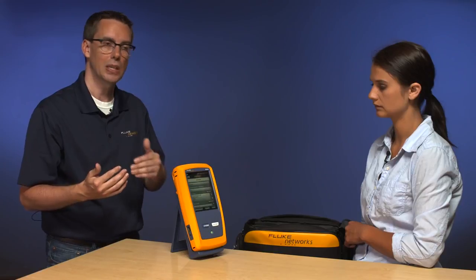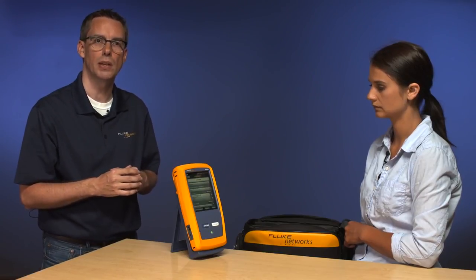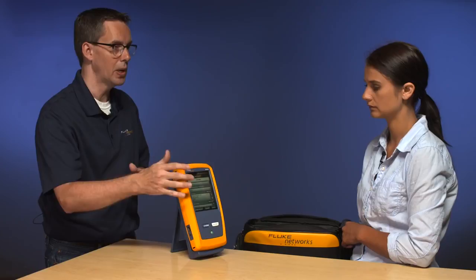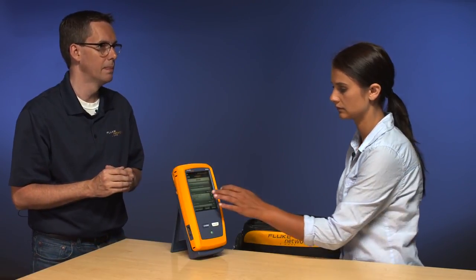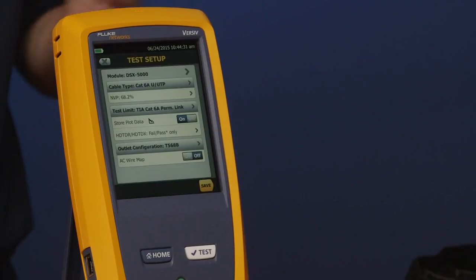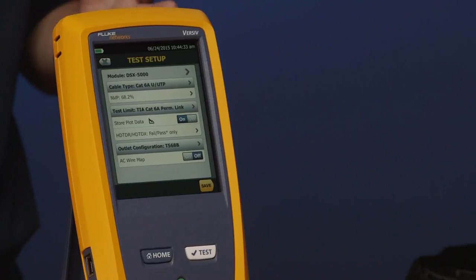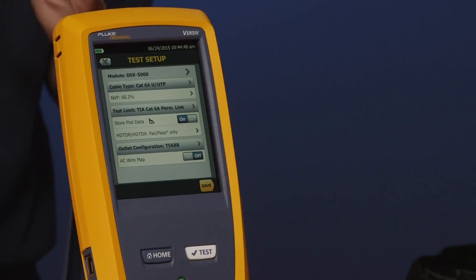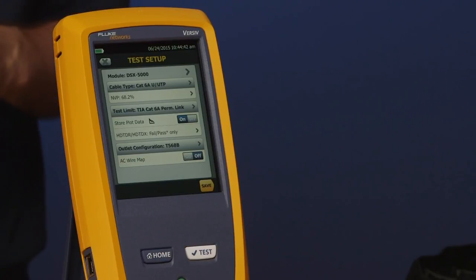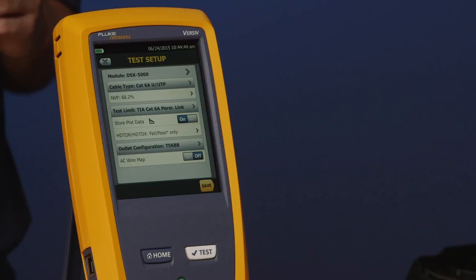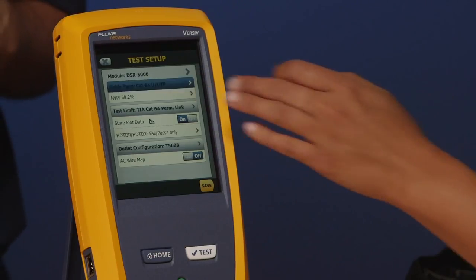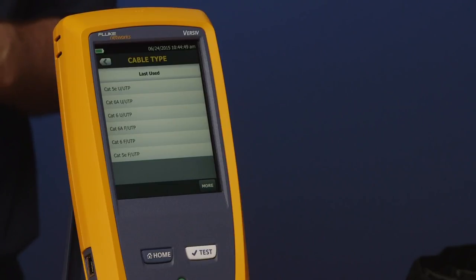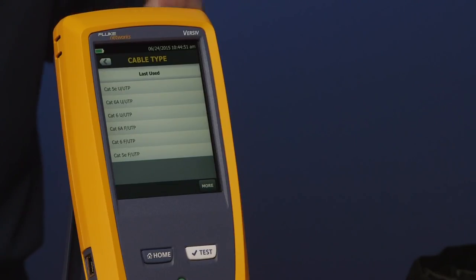We're going to change our test setup. It's defaulted to CAT 6A permanent link — we want CAT 5E permanent link. Go ahead and tap setup. This screen is going to seem very familiar to you if you're a DTX cable analyzer user, and that's deliberate. There are enhancements in there, but we don't want to make it too radically different. Go ahead and tap cable type. This is our first thing we're going to change. We have our last use list on here, which is handy to have.